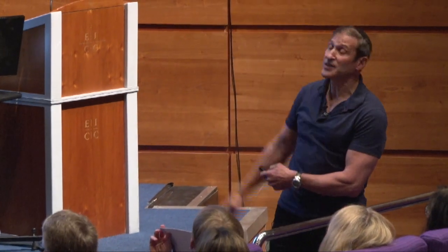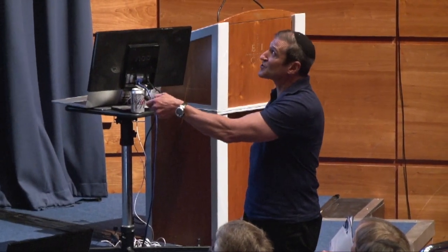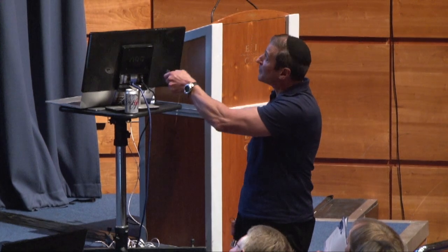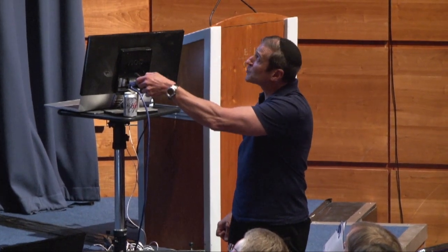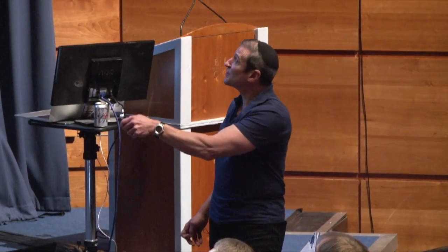Because today, in the old days, it was hard to get any of this information. Today, all the manufacturers provide the information to us. And they'll provide you these kinds of plots. And they'll show you this is a log scale, this is a linear scale. But they'll show you this is the magnet. This is the center of the magnet. That's 1/2 of it. The patient would come in this way. And this is 1/10 the exposure. RF is that. This is 100. This is 1,000. Does that make sense? And this is distance. This is 1/2 meter.